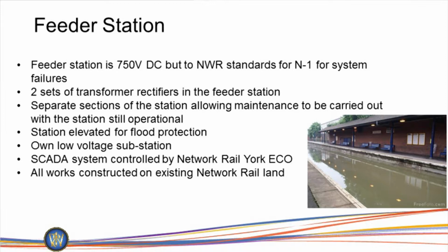The feeder station had to be designed to what they call N-1 standard, which means the maintainer wanted 2 completely diverse electrical supplies, so that if one ring main went out, they could still run the tram train service. As a consequence, the maintainer also wanted N-1 inside the feeder station. Normally on a light rail system you'll have 1 transformer rectifier. We've got 2, so everything is doubled up. There's a backup on a backup. That allowed them, if they needed to do routine maintenance, to take half the feeder station out and run the other section, keeping the tramway running.